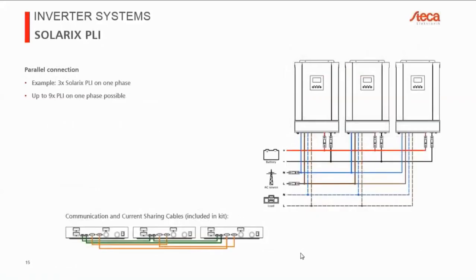So here we have an example for a single phase parallel connection of 3 SOLARIX PLI inverters. They must all be connected to the same battery. This goes for anytime you interconnect multiple PLIs in a synchronized system, you always need to connect them all to the same battery. This is a requirement. Then we have a single AC source, and we simply connect all the inverters in parallel on the AC source. And then same thing goes for the load. The load outputs are all parallelized, and then like that, this is where your consumers are.